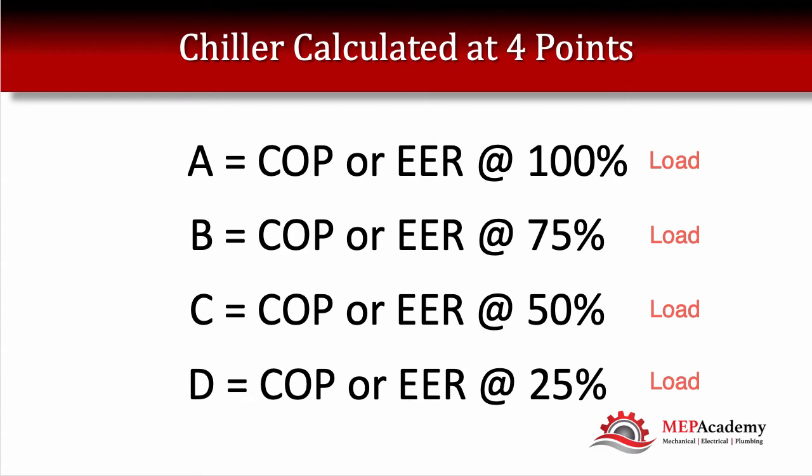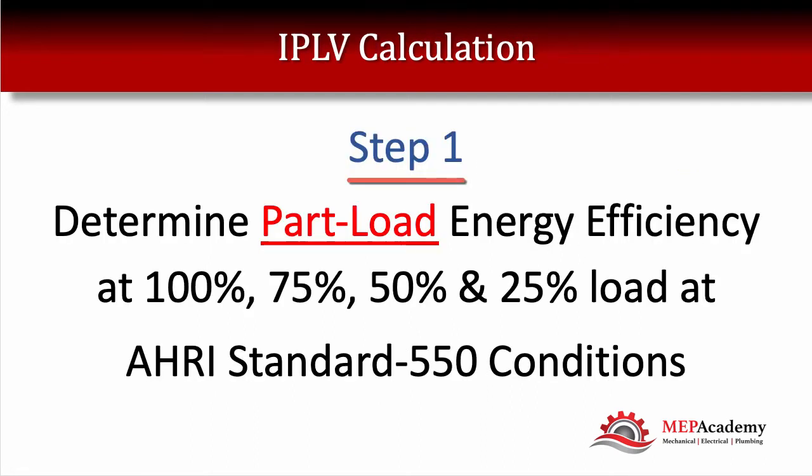These four points represent the load percentages at which the chiller runs. When it's running at 100% load we put that EER into the calculation, and we also include the EER when running at 75%, 50%, and 25% load. Step one is to determine the part load energy efficiency value at these four running loads: 100%, 75%, 50%, and 25%.